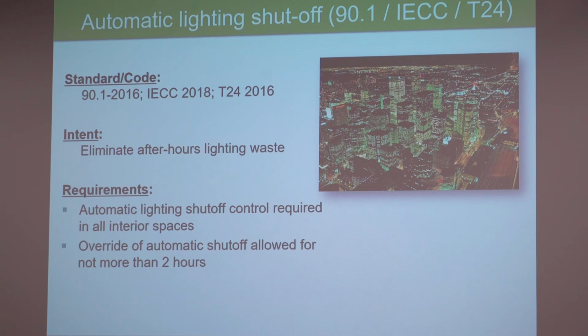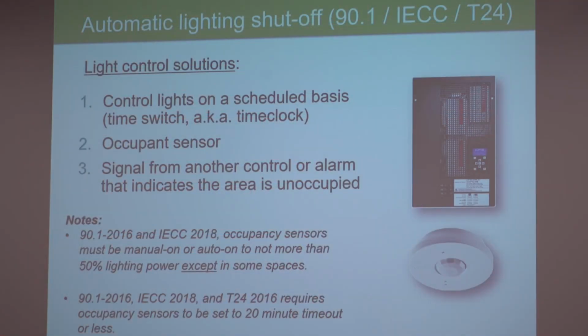Now what are the control requirements? There's a requirement for automatic lighting shut-off. It's in ASHRAE and IECC. The intent here is to eliminate after-hours lighting waste. The requirement is basically that lighting in interior spaces has to be automatically shut off, and you can override that automatic shut-off by up to 2 hours. The common ways to achieve this are either with a time clock or time switch, or an astronomical time clock or astronomical time switch, or occupancy sensors. It's becoming more common to use occupancy sensors now. And then they allow a third way, a signal from another control or alarm system that indicates the area is unoccupied. Yes?